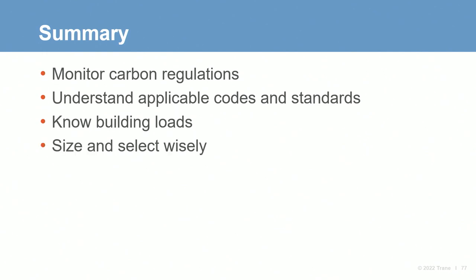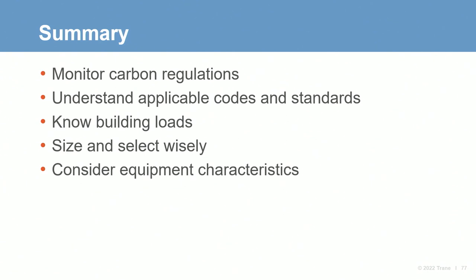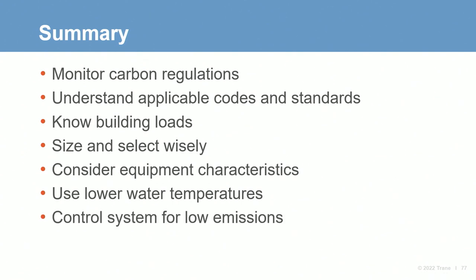Size and select units and system configurations wisely, considering system performance, reliability, and footprint. And consider equipment characteristics, including ambient limitations and expected defrost periods. And also use lower water temperatures for heating and reduce energy and emissions. And lastly, control the plant to maintain low emissions with sequences that incorporate the carbon emissions break-even point. We hope that we provided you with enough useful guidance to help you meet your customers' needs as they electrify their heating systems. So that is our overview of air-to-water heat pump system design.